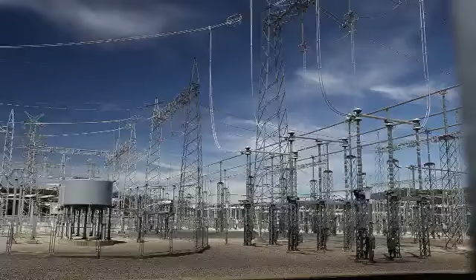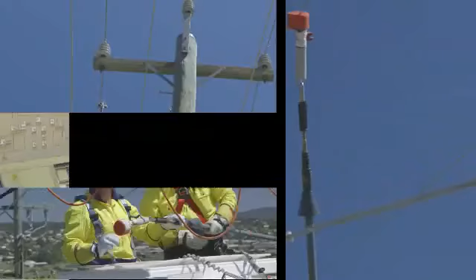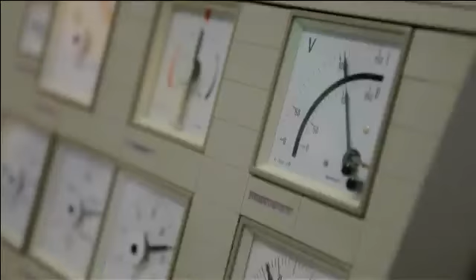Although constructed according to strict fire safety regulations, substation control buildings can also catch on fire. A substation fire can involve equipment energised to high voltage levels, and toxic fumes can be given off by burning insulation material. After reporting the incident to your communications centre, wait for the local electricity authority to arrive to isolate electricity supply to the substation. Entry should not be attempted until the power has been isolated and the OK has been given.